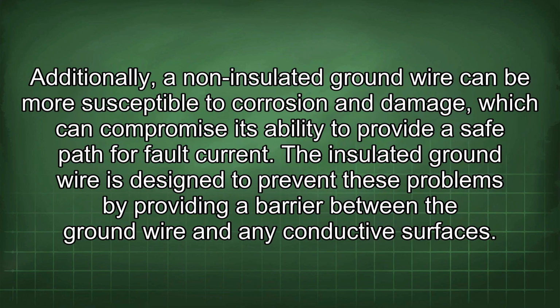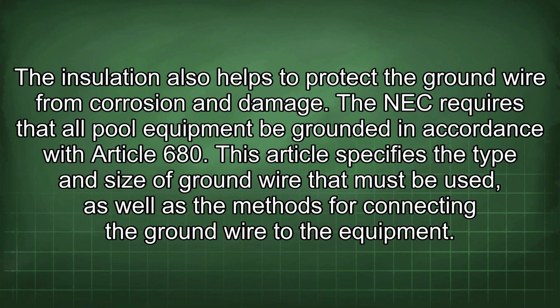Additionally, a non-insulated ground wire can be more susceptible to corrosion and damage, which can compromise its ability to provide a safe path for fault current. The insulated ground wire is designed to prevent these problems by providing a barrier between the ground wire and any conductive surfaces. The insulation also helps to protect the ground wire from corrosion and damage.